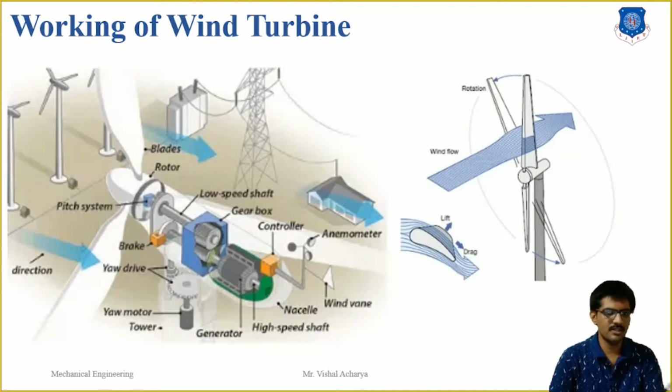The output voltage of the electrical generator is given to the rectifier, where the alternator output gets rectified to direct current. This rectified direct current output is given to a line converter unit to convert it into a stabilized AC output, which is ultimately fed to either the electrical transmission network or a transmission grid with the help of the step-up transformer. An extra unit is used to give power to internal auxiliaries of the wind turbine like motor, battery, etc. This is called the internal supply unit.